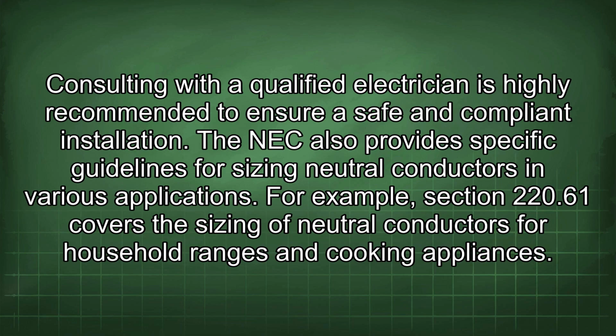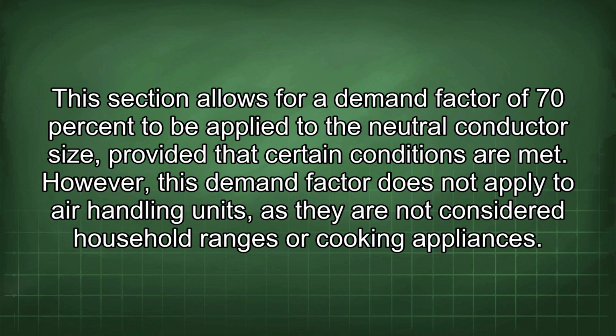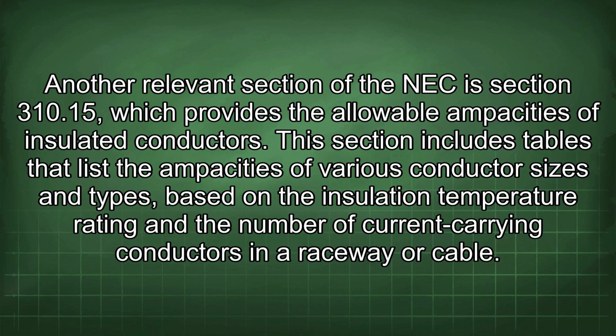The NEC also provides specific guidelines for sizing neutral conductors in various applications. For example, Section 220.61 covers the sizing of neutral conductors for household ranges and cooking appliances. This section allows for a demand factor of 70% to be applied to the neutral conductor size, provided that certain conditions are met. However, this demand factor does not apply to air handling units, as they are not considered household ranges or cooking appliances.